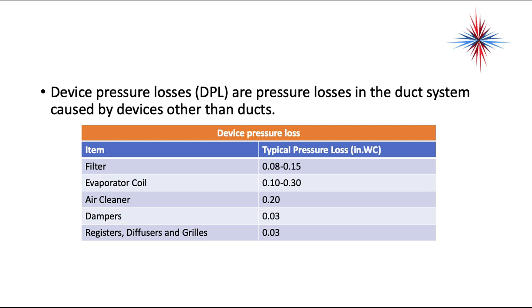Device pressure losses are pressure losses caused by devices other than ducts — for example, an evaporator coil can have a pressure drop of 0.10 to 0.30 inches water column. If you have an evaporator coil at 0.30 and a total external static pressure of 0.5, you only have 0.20 remaining. Adding an air cleaner to that coil at 0.30 could use up your entire 0.5 budget. You may have to make ductwork adjustments and modifications.